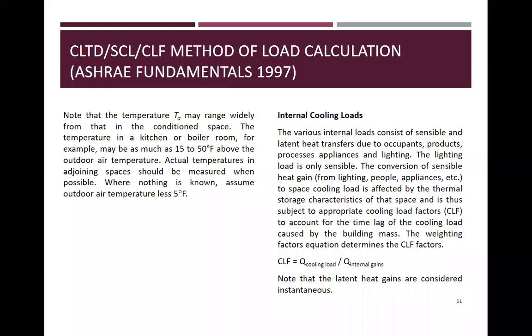Now, next is the internal cooling load. Ito. The various internal loads consist of sensible and latent heat transfer due to occupants, product, processes, appliances, and lighting. The lighting load is only sensible. The conversion of sensible heat gain from lighting, people, appliances, etc. to space cooling load is affected by thermal storage characteristic of that space and is thus subject to appropriate cooling load factors to account for the time lag of the cooling load caused by the building mass.